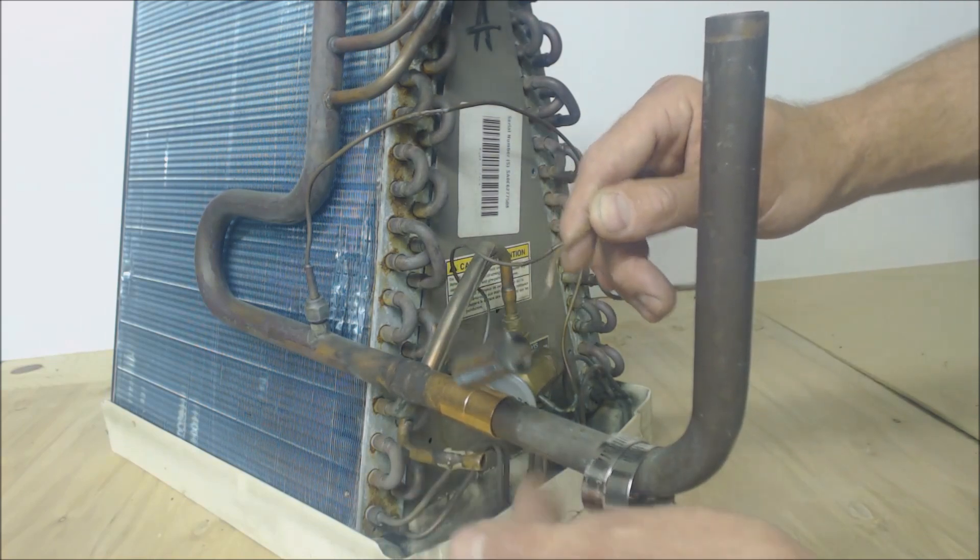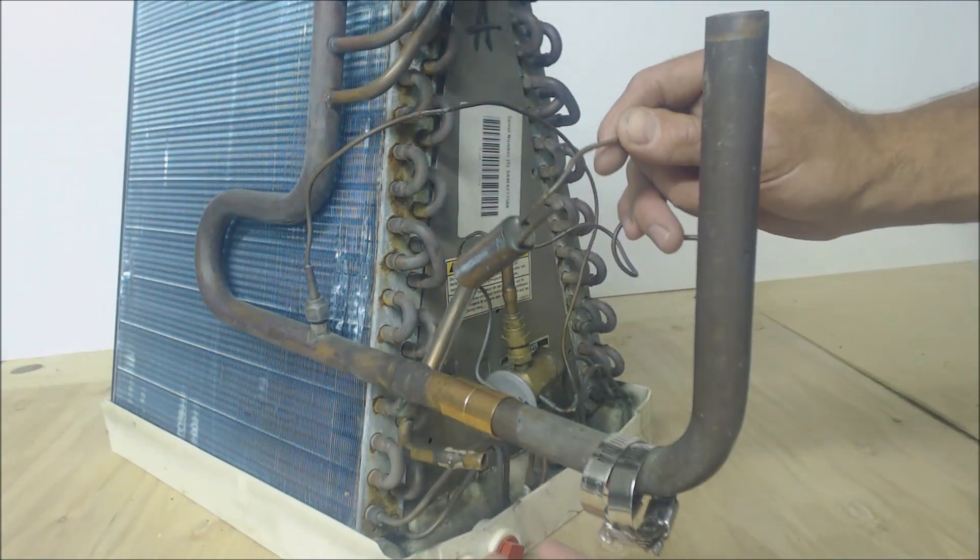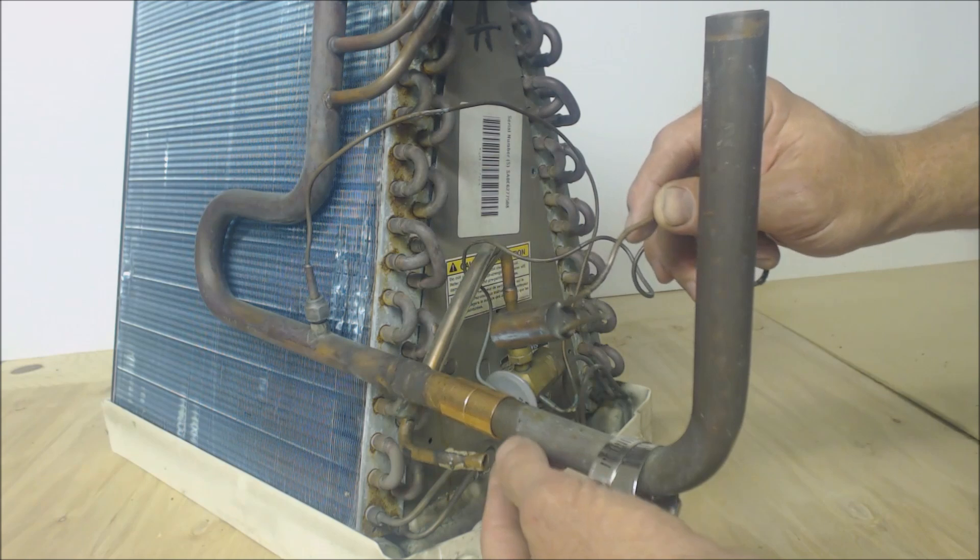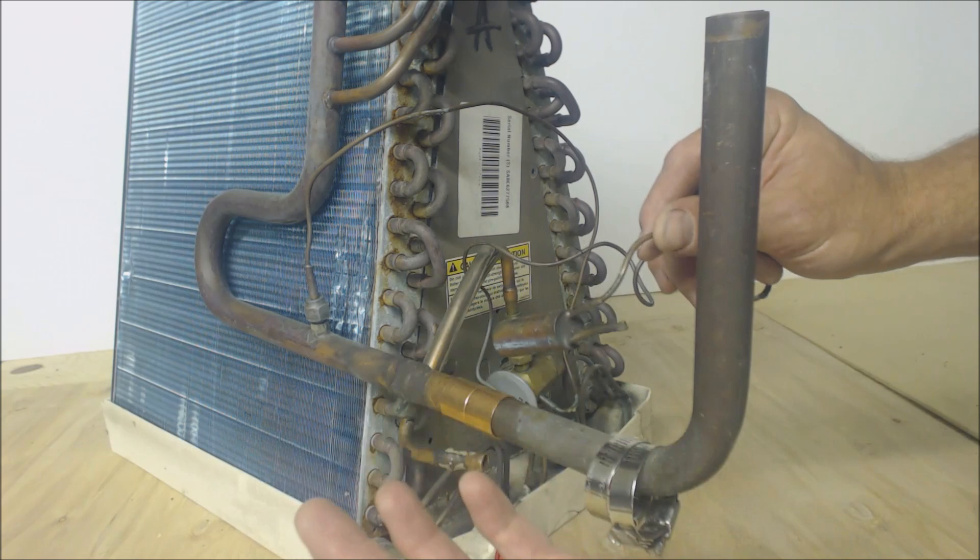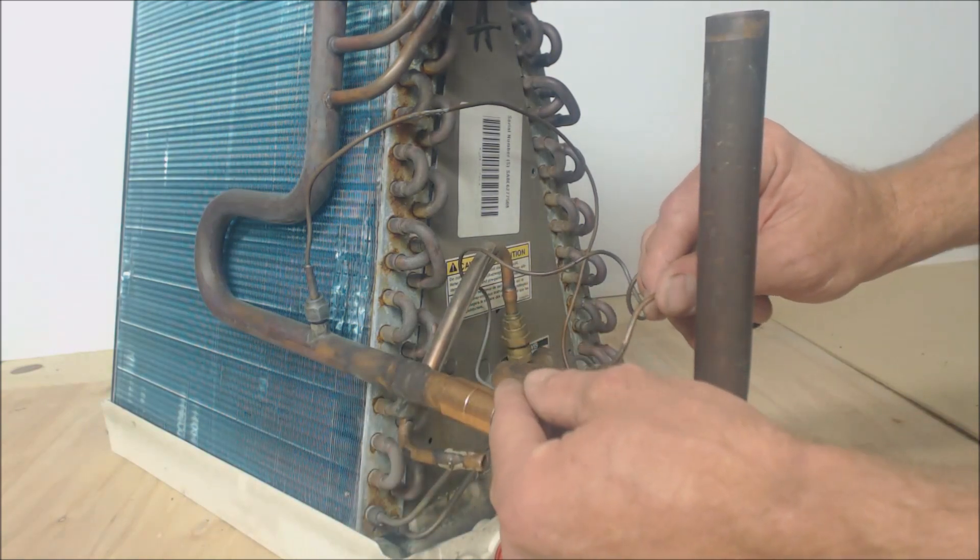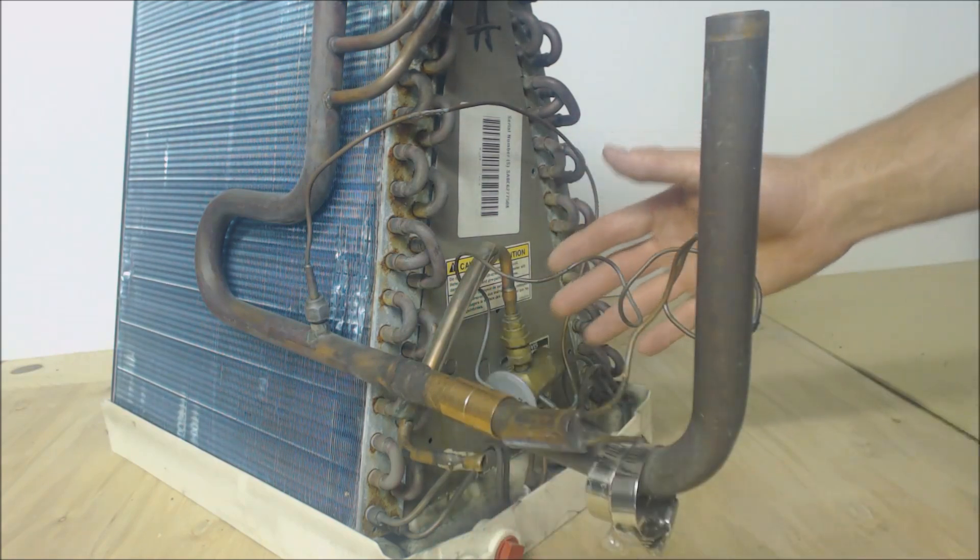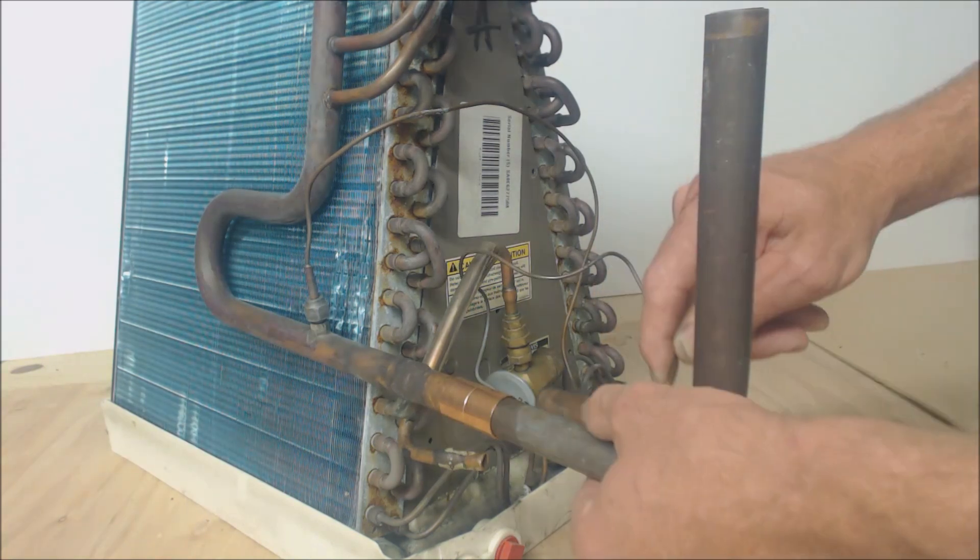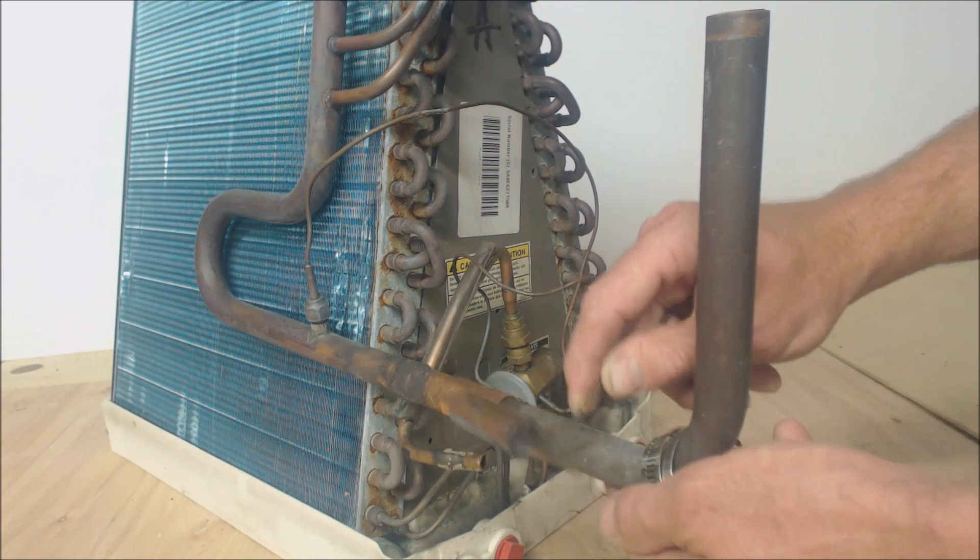We've all cut apart lines after we've recovered the refrigerant and found there's a bunch of oil on the bottom. That oil could create some insulation value and might be half a degree off. This bulb is helping the TXV sense to control the superheat across the entire evaporator coil.